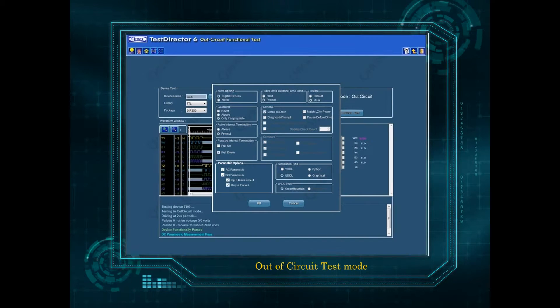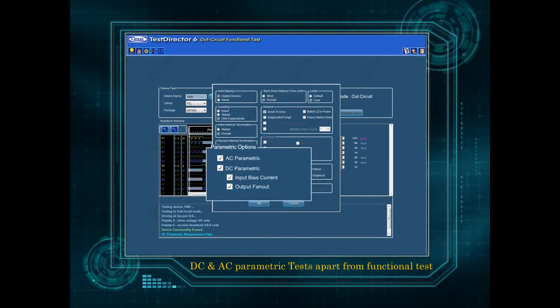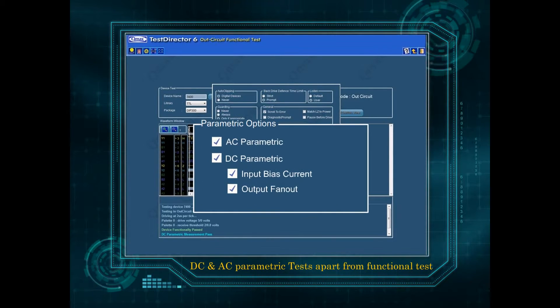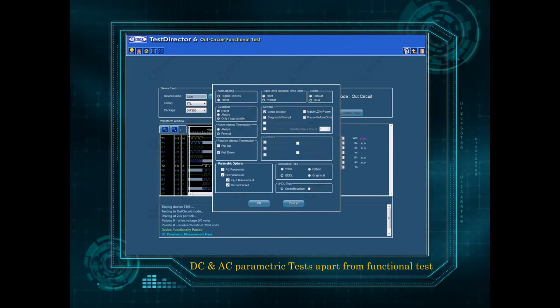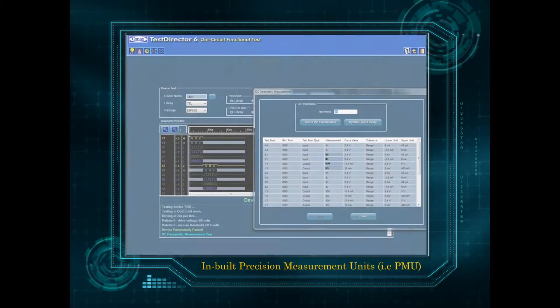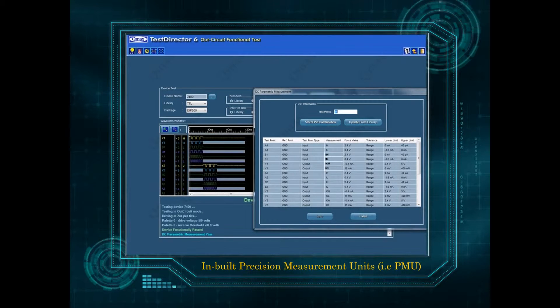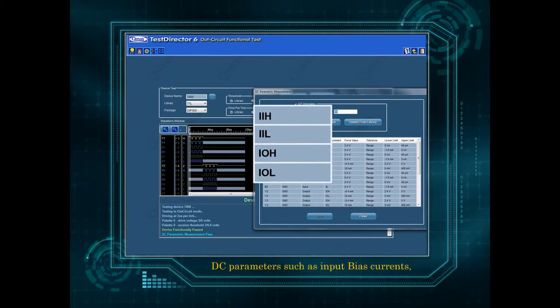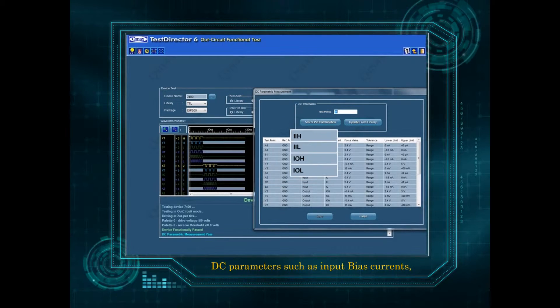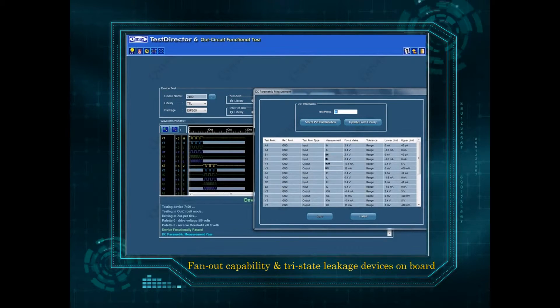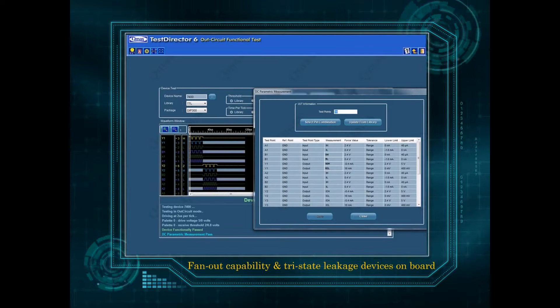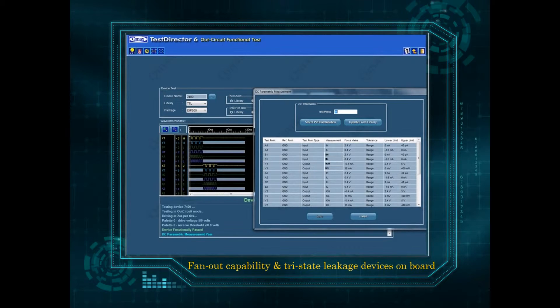Out of circuit test mode includes DC and AC parametric tests apart from functional tests for increased reliability and QC check. In-built precision measurement units, PMU, to test DC parameters such as input bias currents, fan out capability, and tri-state leakage of devices on board.